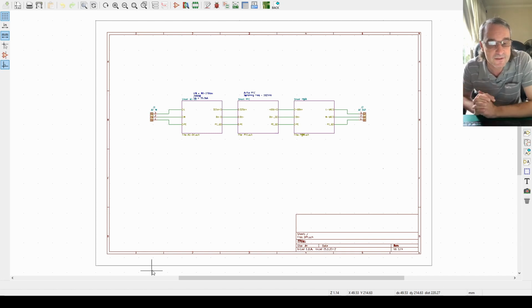It's got a variable time setting, and you can take the control voltage input, which is normally 110 if you've done it properly, or 220. I prefer that they design with 110, and you will carry that 110 through a few cycles. Anything up to normally a second or second and a half that you can set it for, but I would never set it that long, because if your power dips for a second or a second and a half, you've lost your power provider in general. Well, that's my reason.